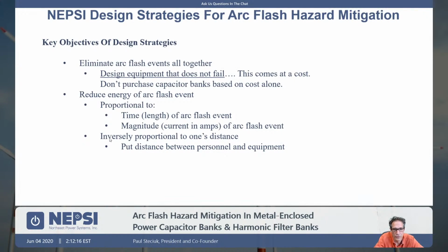What can be done on site? The energy associated with the arc flash event drops off by the inverse square of the distance. So putting the metal enclosed system out in a switchgear yard where nobody is standing and people do not hang out is a great place. Put a metal enclosed capacitor bank inside an e-house, inside the electrical room, and that's where people like to hang out. So we always say, put the capacitor bank outside, put it out at a distance, and in so doing, you're removing the hazard from within a location where people may be hanging out and putting it outside in the switchgear yard. So this is a site type of condition.